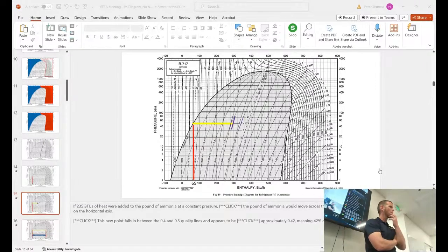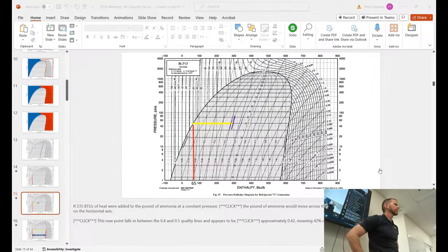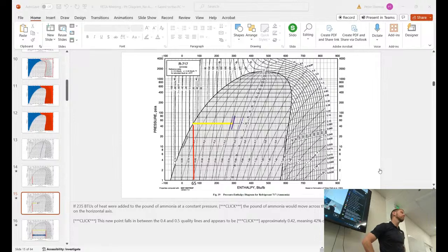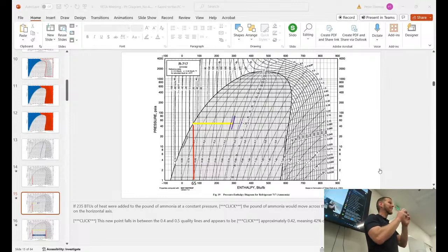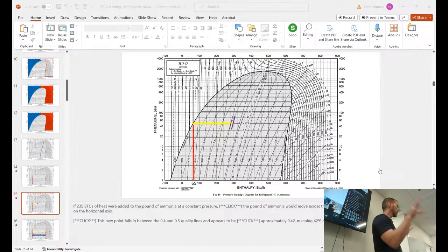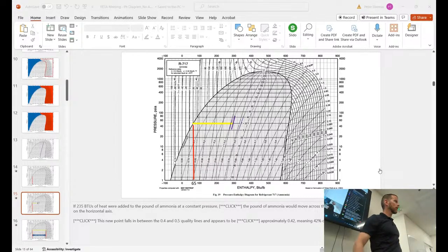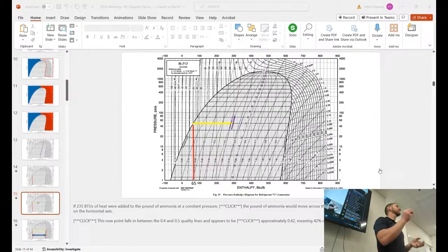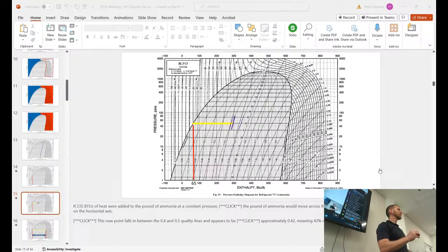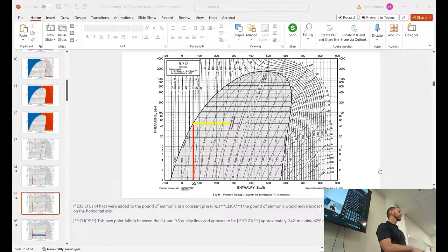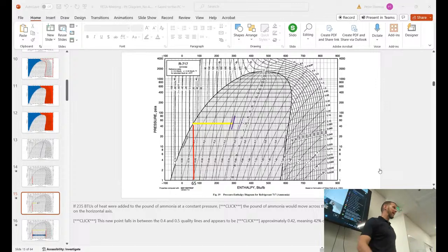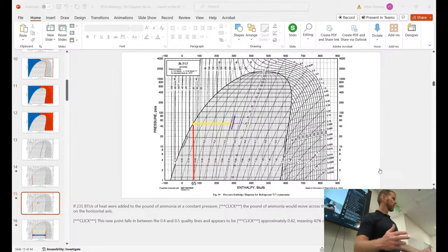Any other questions? In a DX evaporator, you wouldn't be starting all the way to the left, but in a flooded or recirculating system you would — because you expand down to that point F, and then your one pound of ammonia gets divided. The vapor goes right back to the compressor, and the pure liquid goes to the evaporator. So you are getting pure liquid. In a DX system it gets more complicated because your pound of ammonia gets divided in surge drums, accumulators, and circulators.